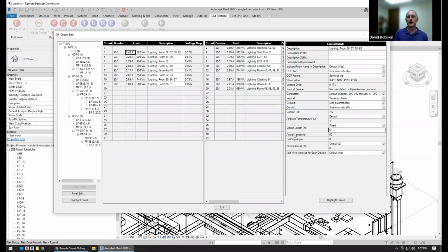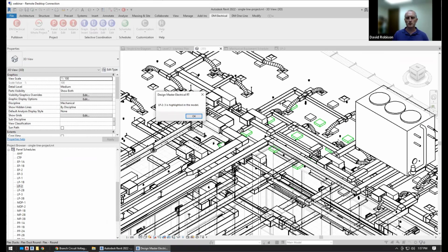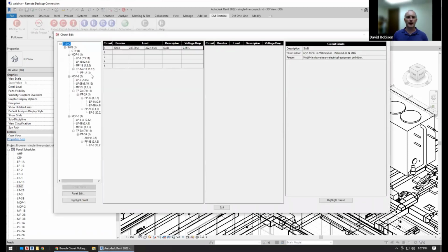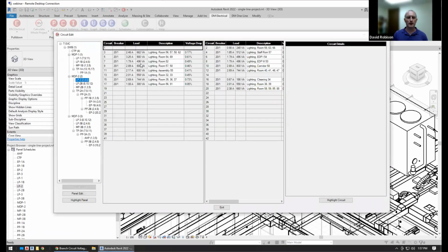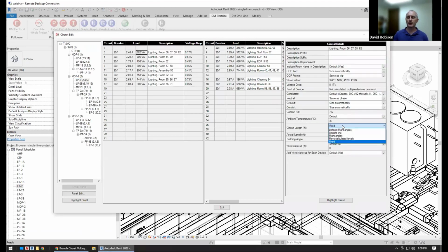For branch circuits, it becomes a little bit tricky. For a feeder, this is really simple because you have a single panel and it's just the distance to that panel from the other panel. For a branch circuit, you've got multiple devices. If we highlight the circuit, there's the question, what is the length that we're even using? What are we going to use that length for? Is there any branching happening? So what we're doing when we're doing our automatic calculations is that we are calculating the average distance.